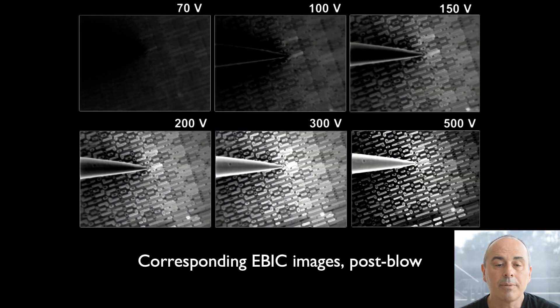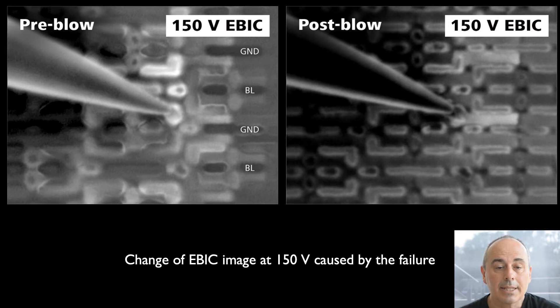The next set of images are the corresponding EBIC images after creating the failure. At a first glance, we see the gate light up in addition to the gate contact as well as its neighboring gate. A closer look reveals a more drastic change of the complete structure in the next image. Let us now have a closer look at this change and select two images taken at 150 V beam voltage, one before and one after the blow. The change is most obvious at beam voltages of 150 V and 200 V.